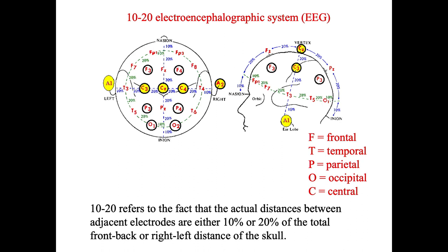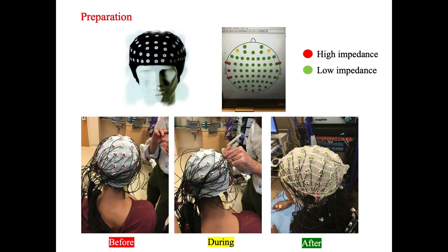There are many different techniques to record the EEG — we can use a cap, for example. As shown in this slide, we use a 64-channel cap to do the EEG recording. A very important step is the preparation of the cap or electrode, which is done to reduce the impedance of the electrodes. In this slide, the red color means very high impedance, and the green color means lower impedance, which we can use for recording.